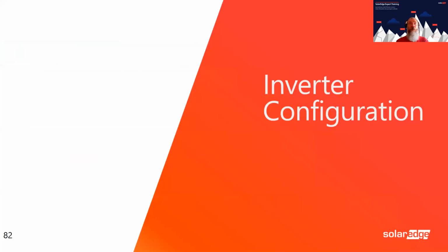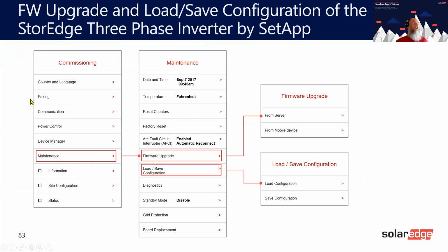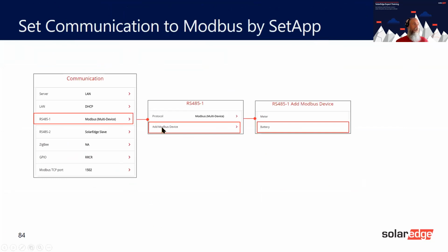And when it comes to the inverter configuration, this is where you would go in the commissioning. So maintenance, firmware upgrade, load save configuration. So load configuration. Then when you've done that, you then set up your meter. You've then got to put the battery in after you've done the meter.